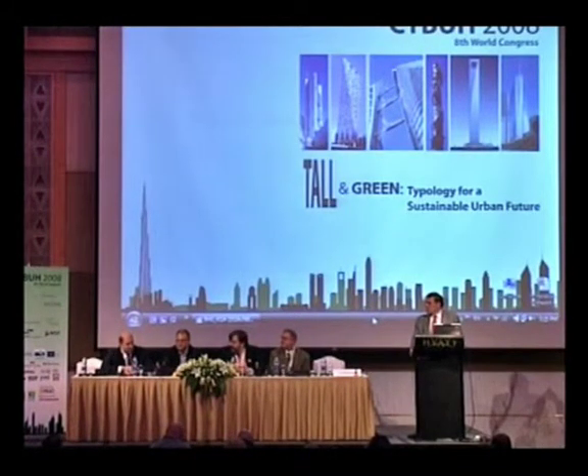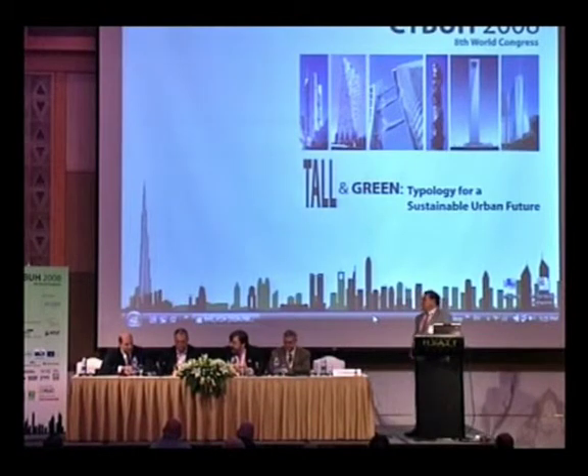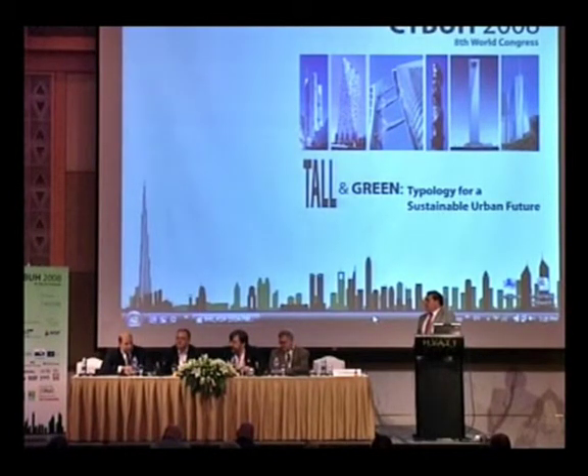Yeah, on your first question, how many of those buildings were sprinklered, is really only the one in Venezuela that was fully sprinklered. And I guess the point I was trying to make here is that we do know that sprinklers in high-rise buildings are quite reliable and quite dependable. But my use of the other examples was to try to illustrate that if and when the day comes, and it would be a rare event, I think, that in a fully sprinklered building you might have a sprinkler system shut off or a riser shut off, maybe for maintenance. At the same time, you have an ignition there that we could see transition into a very large catastrophic event.